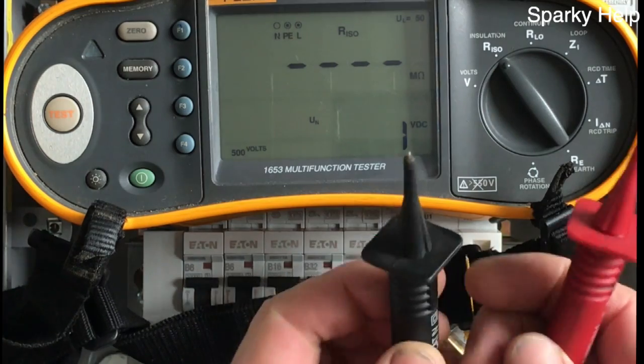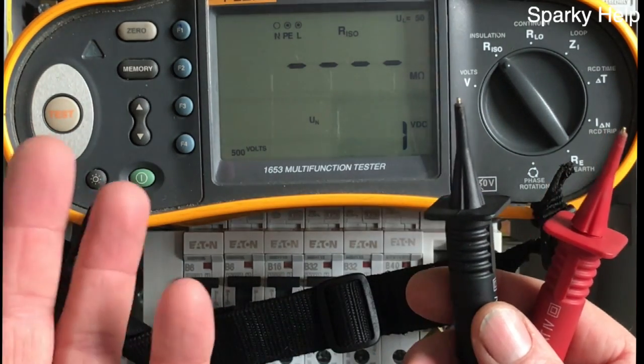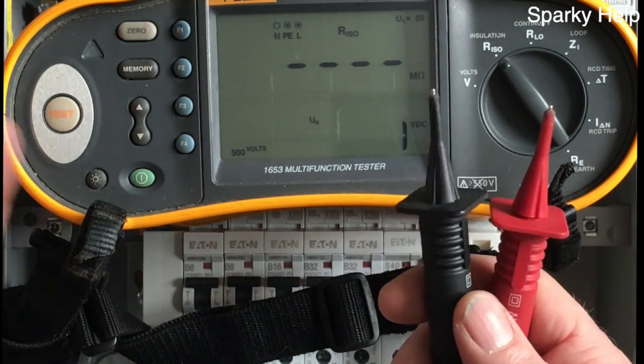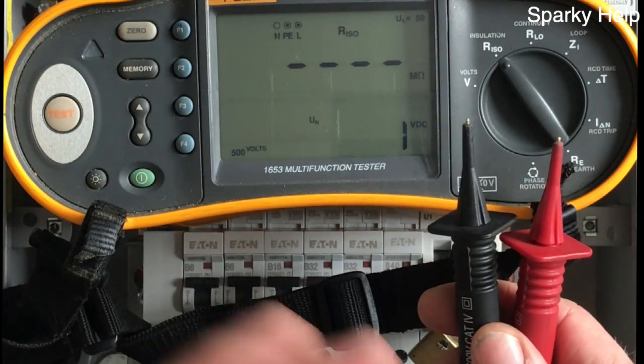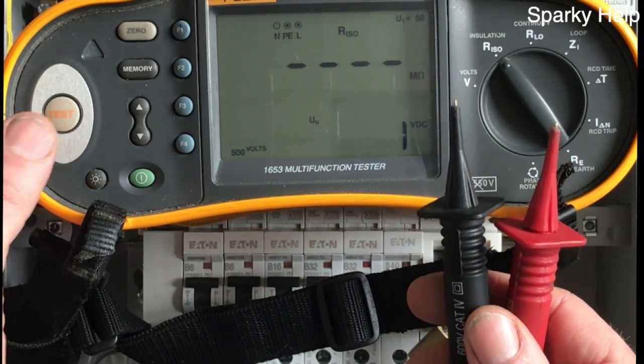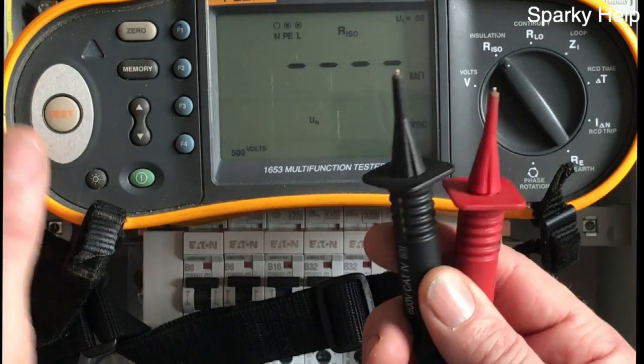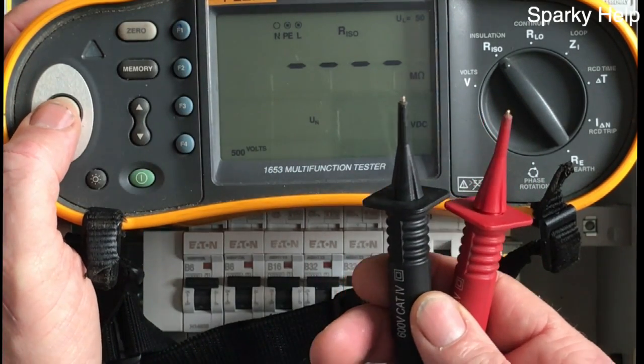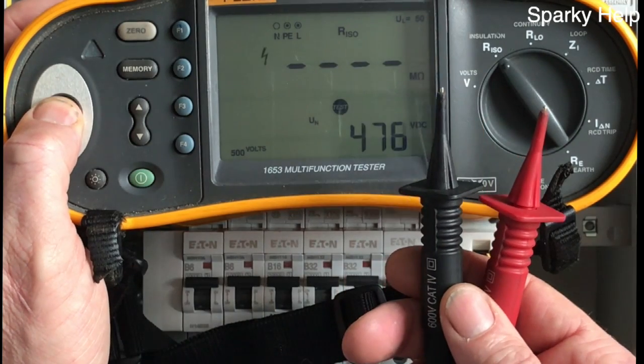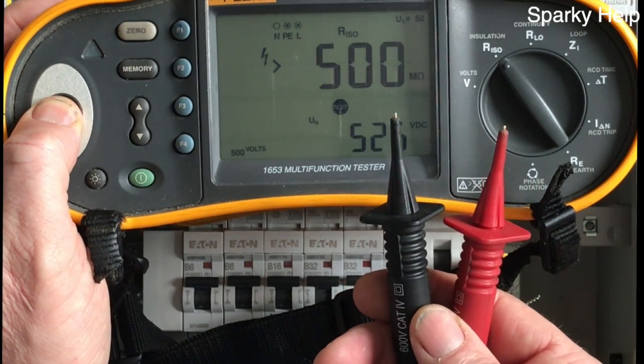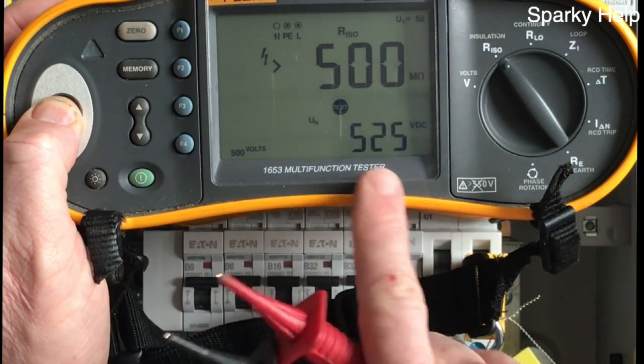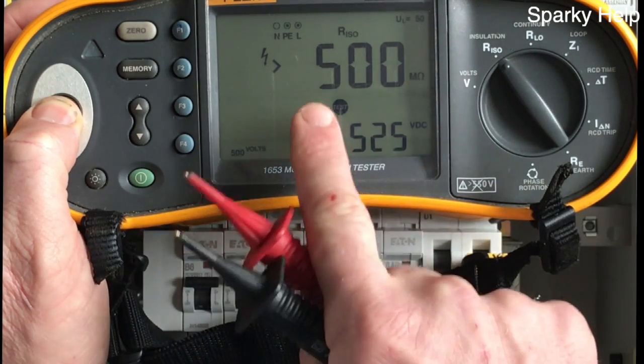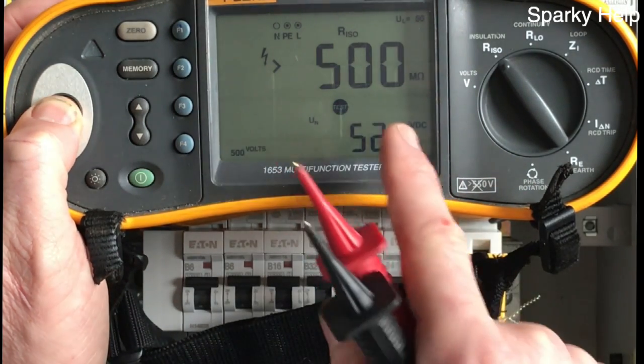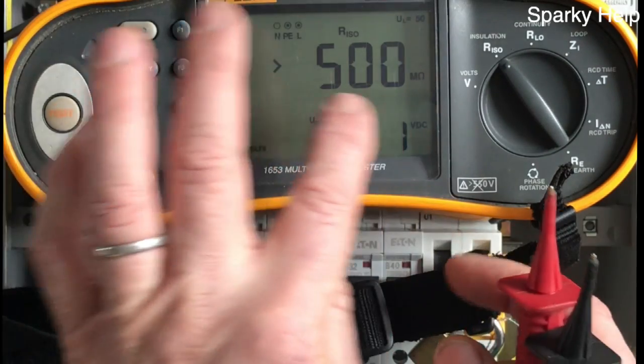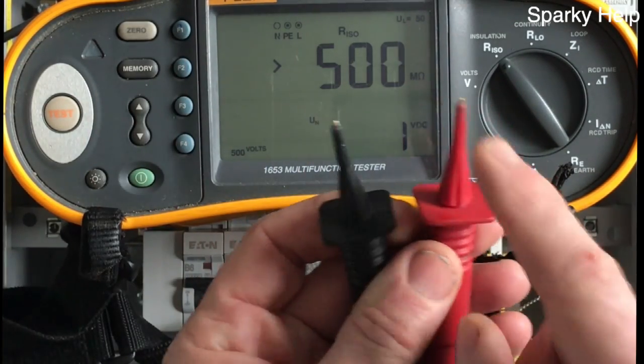As before, what you should always do is verify your meter, especially those people who are going to do exams and things like that. They'll probably be looking for you to make sure it all works, and for your own peace of mind and benefit, to make sure you're not wasting your time. So, leads plugged in as appropriate, where the instructions of your particular meter tell you to. Press the button, and this gives you an open circuit. So what we now know is that the voltage is okay, so the batteries must be okay, and greater than 500 mega ohms is the insulation resistance between these 2 points.